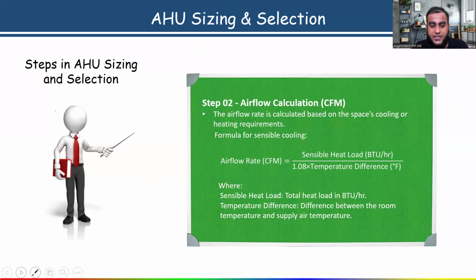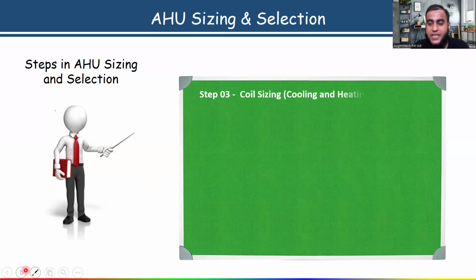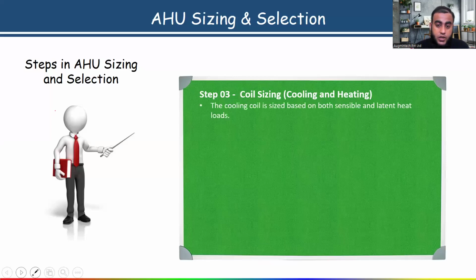Now the next step you have to remember here is coil sizing, meaning cooling and heating coil sizing. The size of a cooling coil or a heating coil is based on both sensible and latent heat load. Here you have to consider both, because inside the room we have to maintain comfort, meaning temperature, and we have to maintain the humidity also. So while doing the coil sizing and calculating the coil capacity, remember the coil is sized based on both sensible heat and latent heat load.